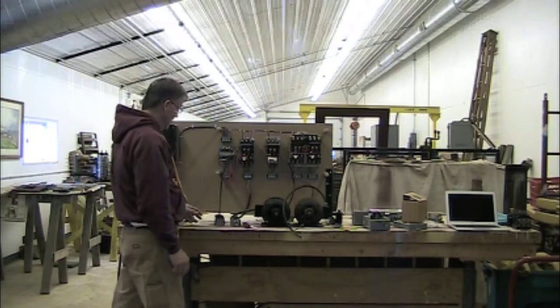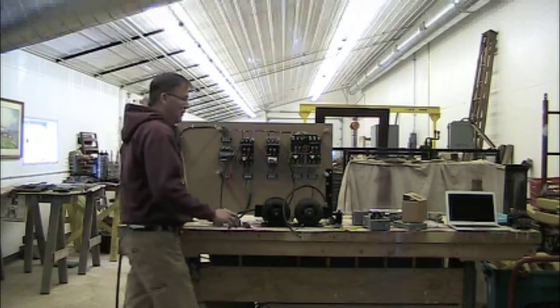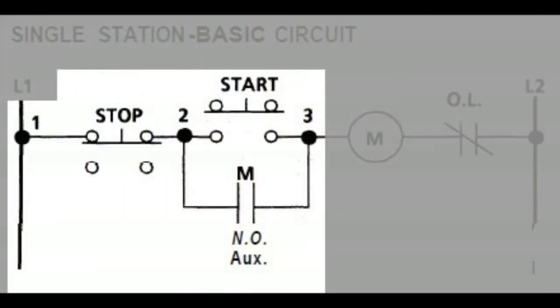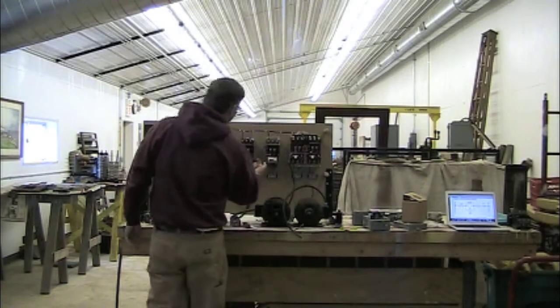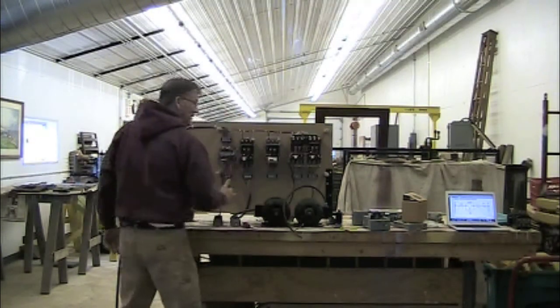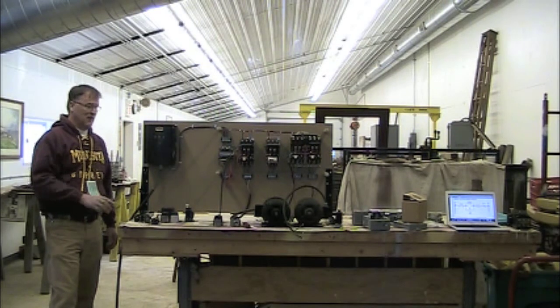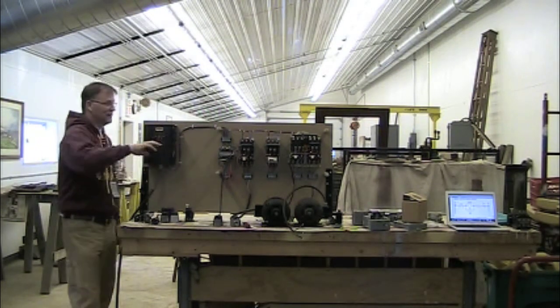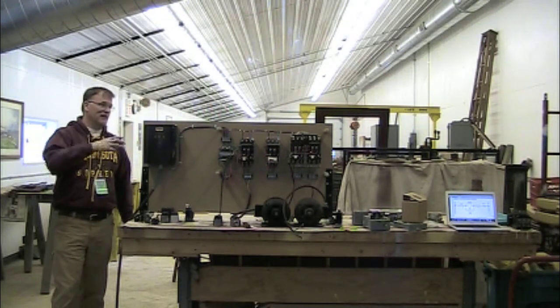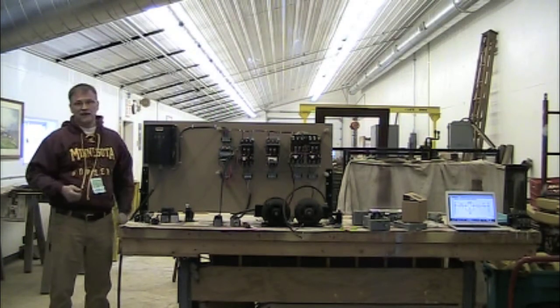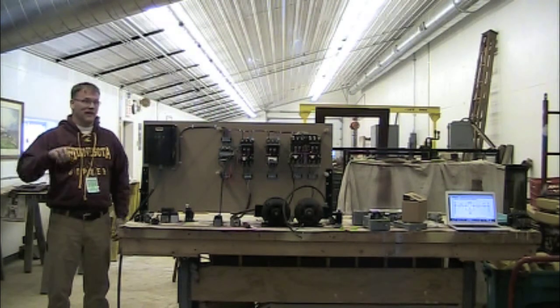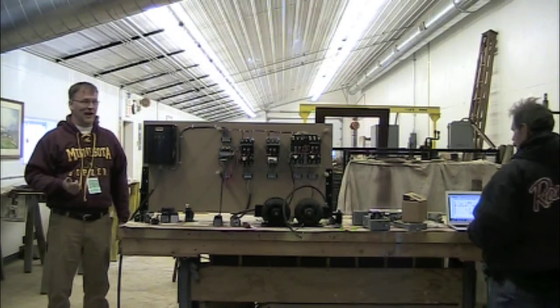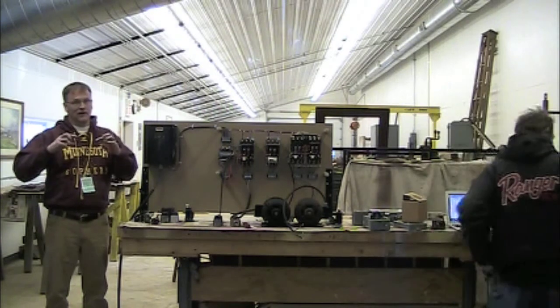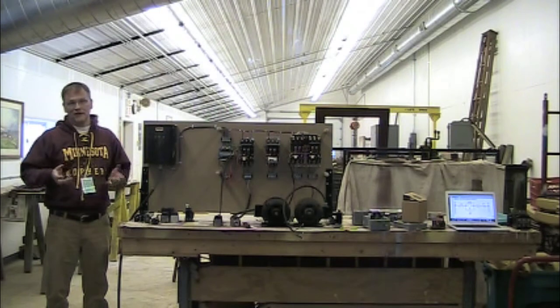Turn on the power and we have start, stop. One thing that a lot of people aren't aware of: the way this is set up, it's always waiting for the input from the start to engage the contactor, but the contactor closes the auxiliary contacts. So sometimes if you're working on something and you don't realize it, you can actuate the contactor. If you just bump that lever, your motor is going to start without touching the start button. Most of these types of starters rely on gravity. They're all designed to be mounted upright. So if you're bench testing this and you have it in a box and you jar it on your bench, you can jar the armature hard enough that it'll close and your motor will start. Like I said, they're all designed to be run vertical because they rely on gravity for some of the force to pull them down. So you can drop the box and your motor will start.